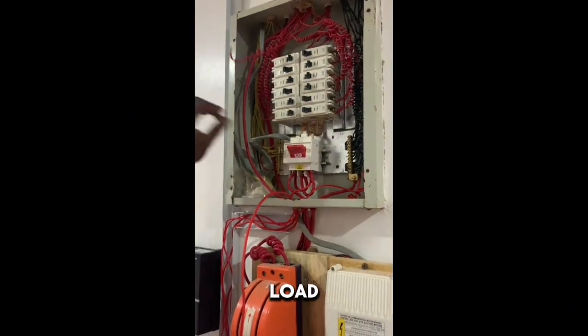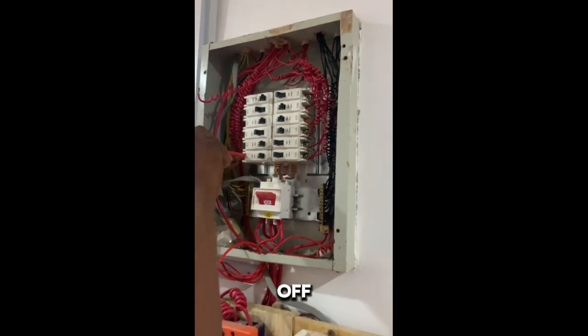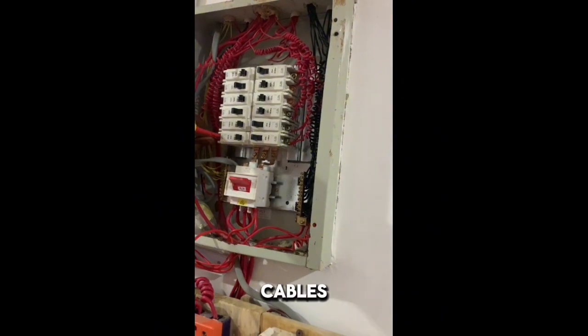Okay, this part, this is where we're concerned about now. So the load shedding, what I'm going to do is take off all these other cables from the DB. This is the fridge. The fridge supply is here. So we need this one with the inverter. All these other ones.